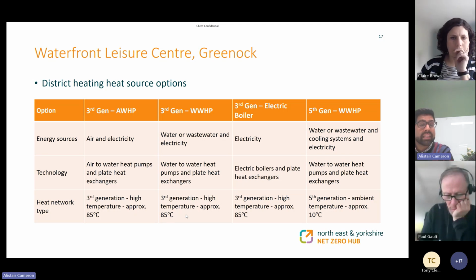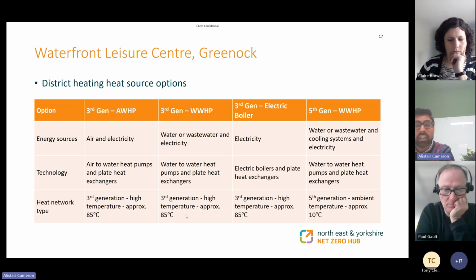So if there was, for example, fabric improvements made to the Waterfront Leisure Centre or fabric improvements made to the GMB building, and that building no longer needed heating at 80 degrees, we could locally adjust that at the local heat pump at the building and essentially take advantage of the efficiencies associated with that reduction in temperature.